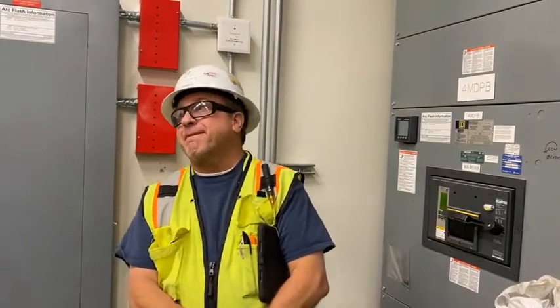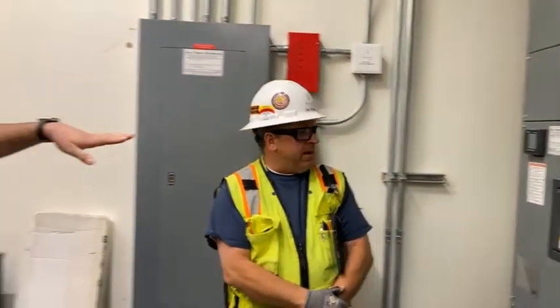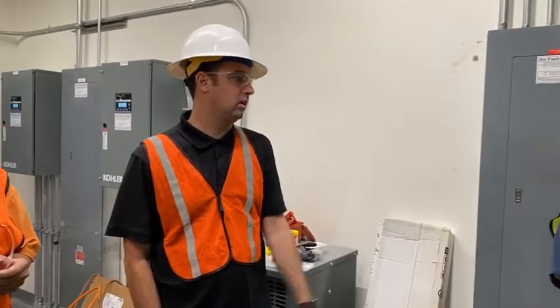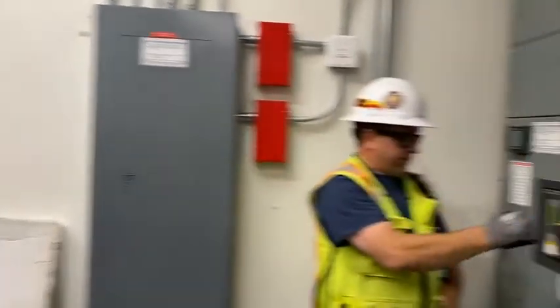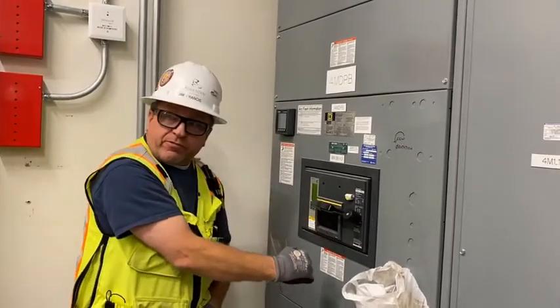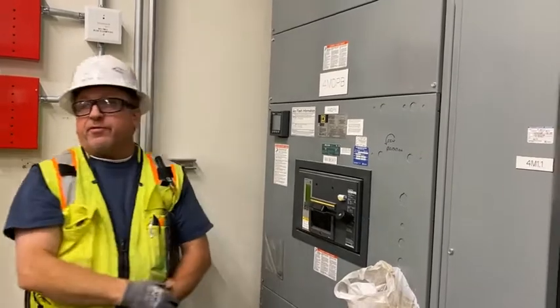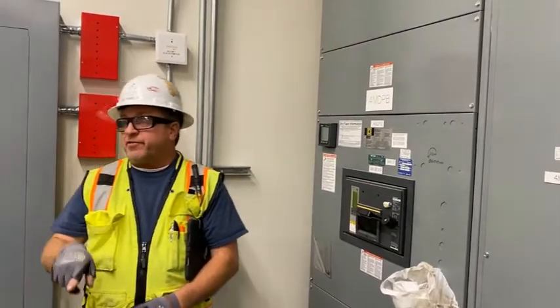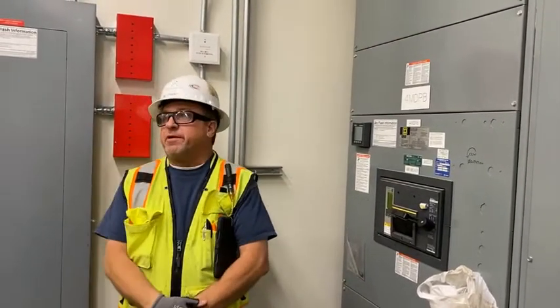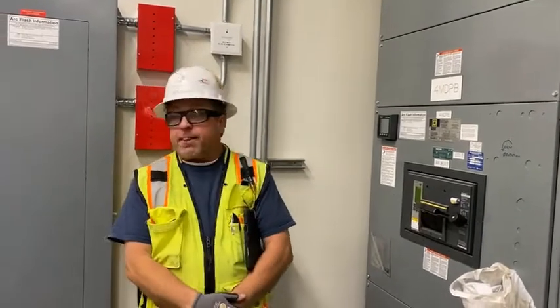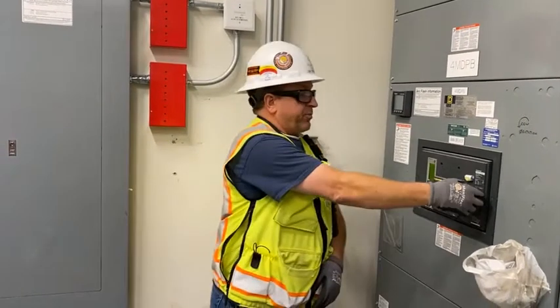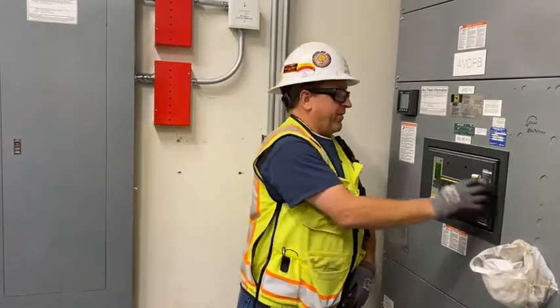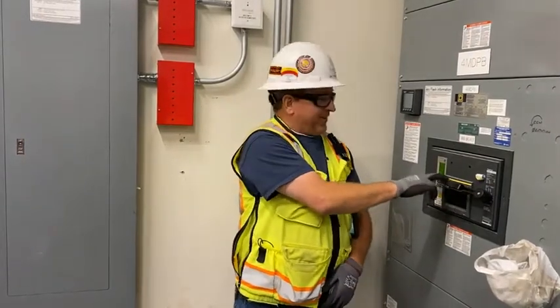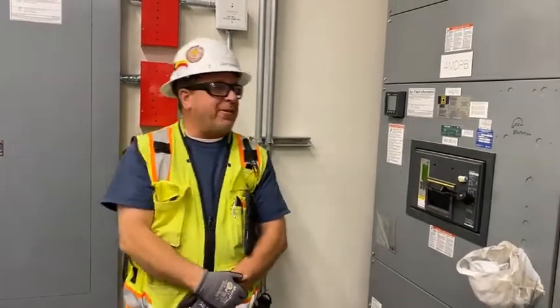So these main breakers here, how do we reset those? Is there anything special, do they just turn off and on? Yeah, if it trips you have to switch it to off and then reset it. They're not like the GE ones where you have to energize the spring, pump it and stuff. So I'm assuming that little arm is just for extra leverage? Yeah, leverage. Most people can't reset that without that leverage thing.